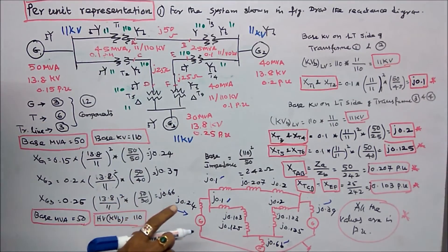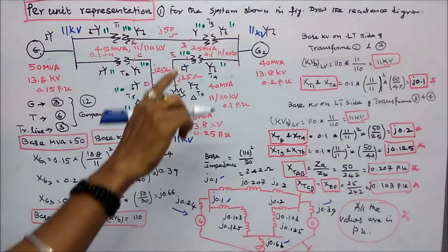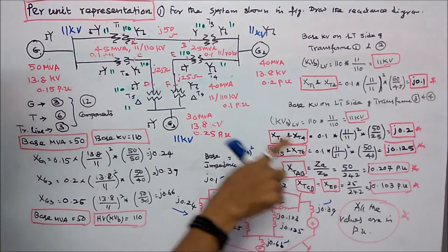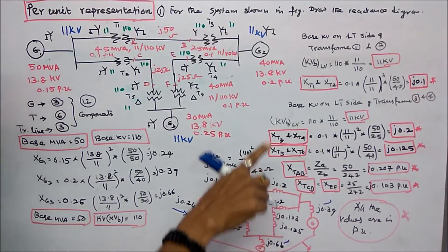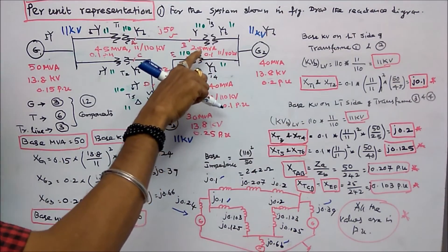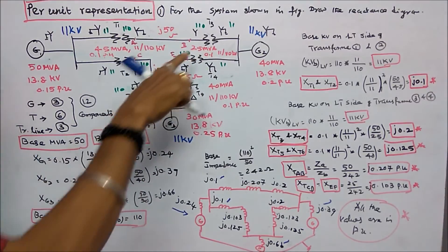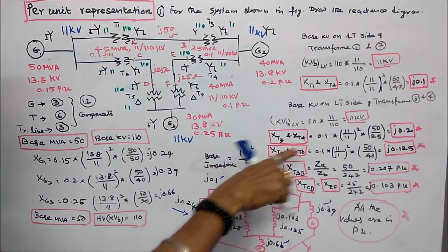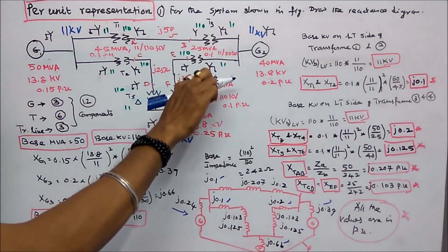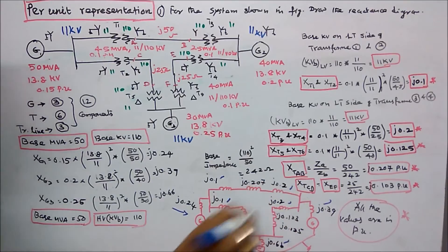For transformers T3 and T4: per unit = 0.1 × (11/11)² × (50/25) = j0.2. Both T3 and T4 are j0.2 per unit.